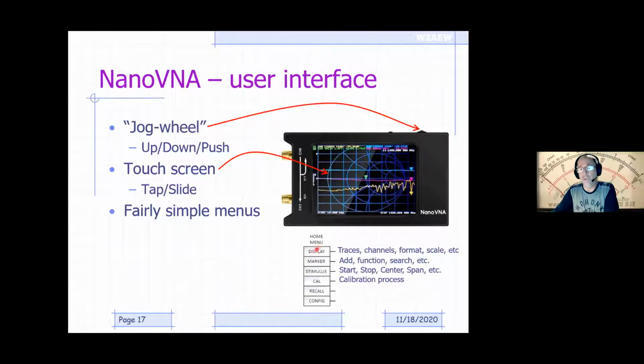Like the display menu allows you to select what traces are visible, what channels those traces are attached to, whether it's channel 0 or channel 1, meaning measuring reflection or transmission properties, and what format and scaling you want to display it in. The stimulus menu, for example, allows you to set the start and stop frequency or a center and span to measure, so you can set up what frequency range you want to measure, etc.